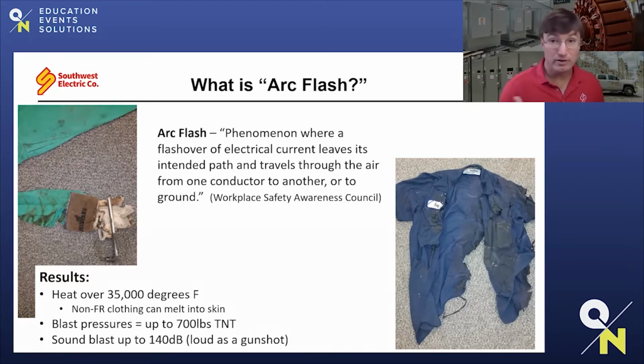The results, as you can tell from these photos, can be disastrous. The photo on the left was a gentleman who was trying to tighten bolts on a power bus that he thought was de-energized. Unfortunately, it was not. And so it arced through his wrench and his body to ground. The result was not only the arc flash explosion and the damage done to the equipment, but also the glove he was wearing was not arc flash rated and actually melted itself into his hand. Fortunately, he was able to survive, but with significant burn marks on his body.